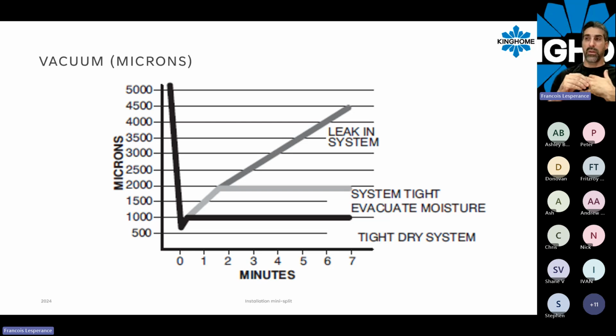So basically, what we're going to do is start the vacuum pump for maybe 10, 15 minutes, and then wait until you reach 500 microns. When it's done, stop the pump and look at your micron gauge. If the microns just increase, going up, up, up, and never stop, never being stable at any point, this is because you have a leak somewhere. You have a leak in your line set, or at your flare nut, somewhere that you must find before you open the valve and bring the refrigerant in.